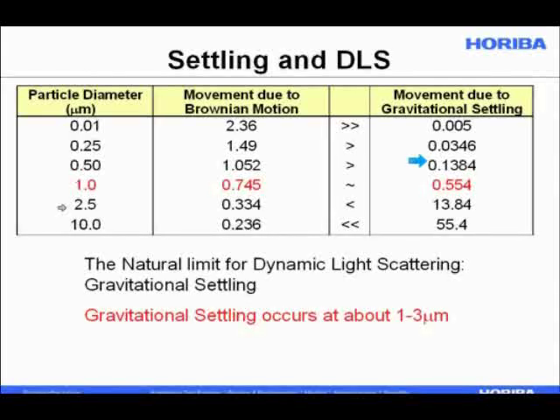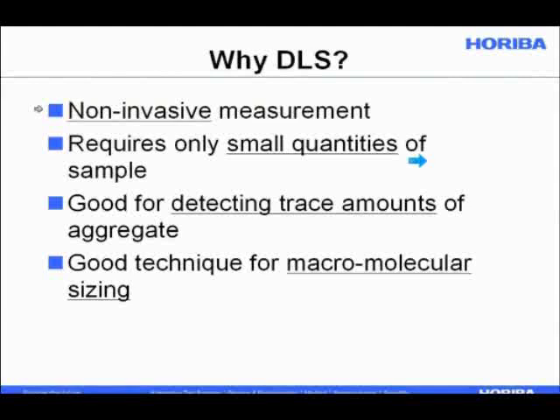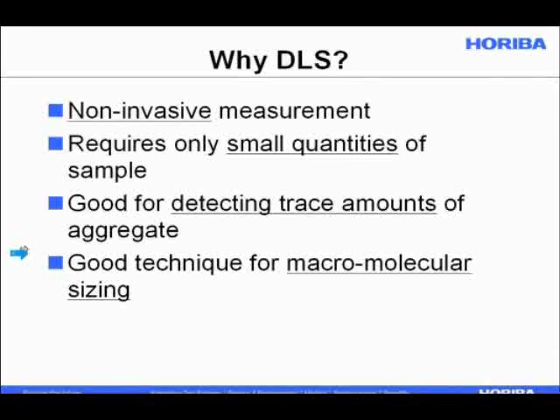Why would you use dynamic light scattering? It's non-invasive — you measure the sample and can still use it for your application or analyze it by a different technique afterward. It requires only small quantities of sample, as little as 10 microliters. It's also good for detecting trace amounts of aggregate. Finally, it's an excellent technique for macromolecular sizing — characterizing proteins, their conjugates, and aggregates.